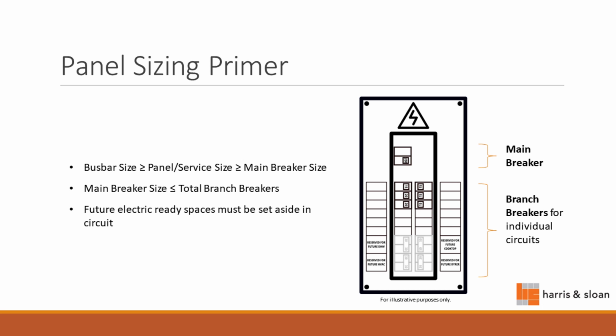The electrical code allows us to take all of these loads and apply a sizing factor, saying we're only expecting that you'll use this type of circuit this much of the time. From those calculations, we get a much smaller number than the sum of all the branch breakers, and that's what we use as our demand load. If that demand load is smaller than our main breaker, we feel fine saying our branch breaker and panel size is enough.